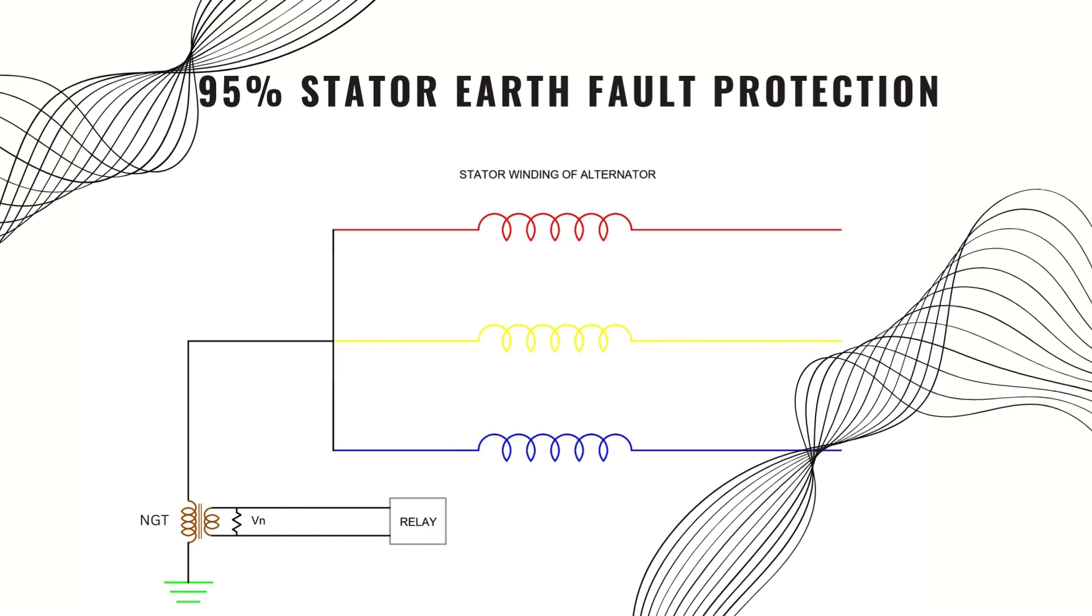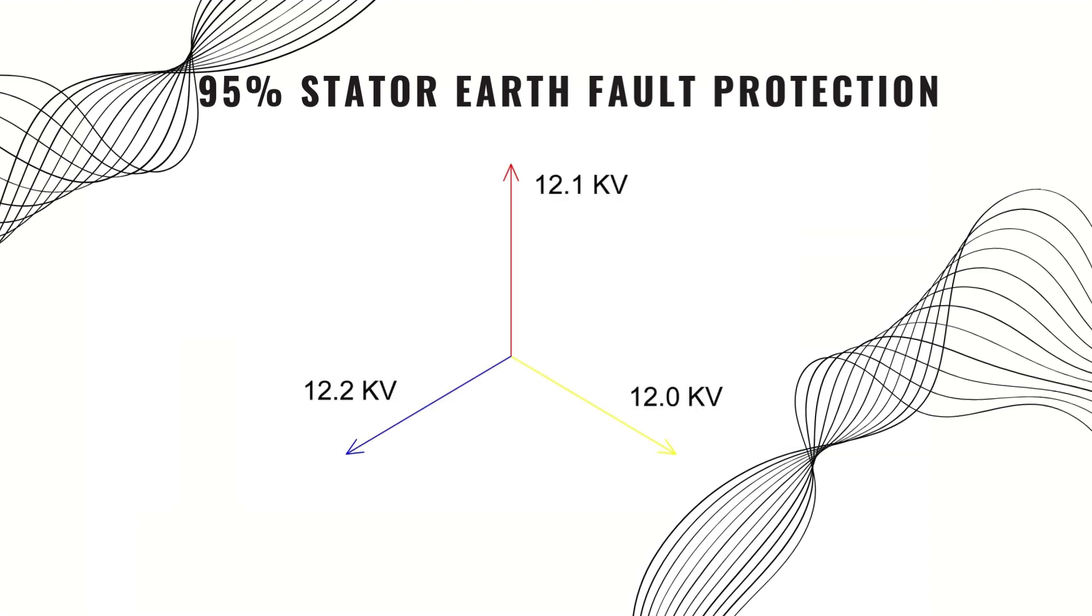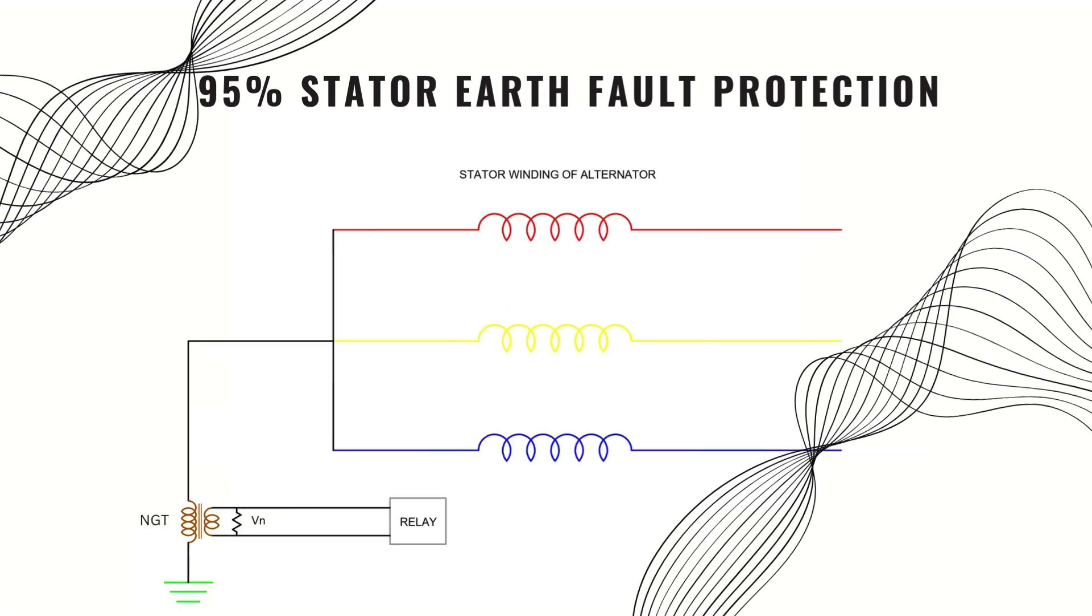In normal running conditions, the voltage across all three terminals is almost the same, but there must be a small difference. This difference is reflected in the neutral terminal. The NGT steps down this voltage. The voltage across the secondary terminal VN becomes almost 0 to 1 volts. This voltage is much less than the predetermined value, so the relay will not trip the generator.